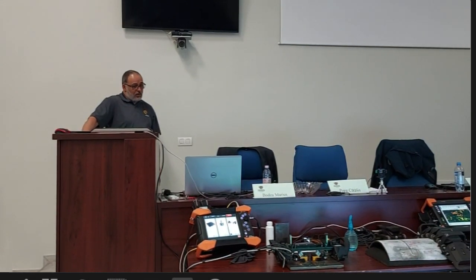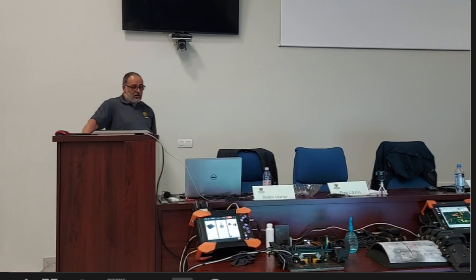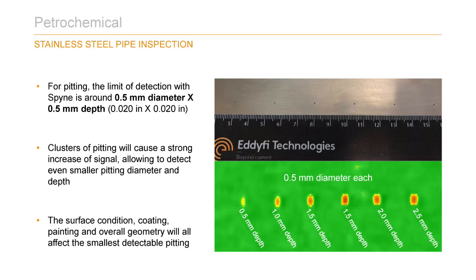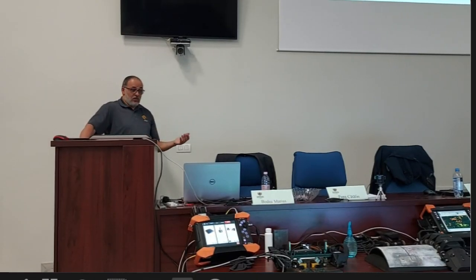Here, for example, you see on the far left of the C-scan a 0.5 by 0.5 pit, which is easy to detect, of course. One thing to keep in mind is that even if we have paint or coating, we are still able to detect this, and I will be able to demonstrate it to you. I have a plate here with different sizes of defects with just a piece of tape on top to create some liftoff and simulate painting. Eddy Current Array doesn't require any specific surface preparation.